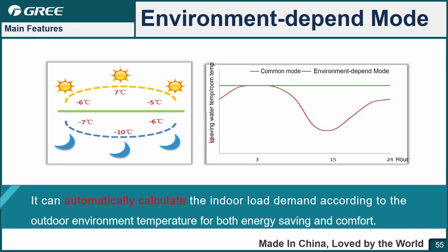Next one is the environment dependent mode. This is automatic control by the temperature change in the daytime and the nighttime, also the season change. For example, in the common mode, the leaving water temperature is flat. You can see no matter what the time is, the leaving water temperature is constant. However, that's not energy saving. However, if you choose the environment dependent mode, in the daytime the unit will output at the maximum. In the daytime, here is the daytime, the leaving water temperature will be lower. However, during the night time, the leaving water temperature will be higher.